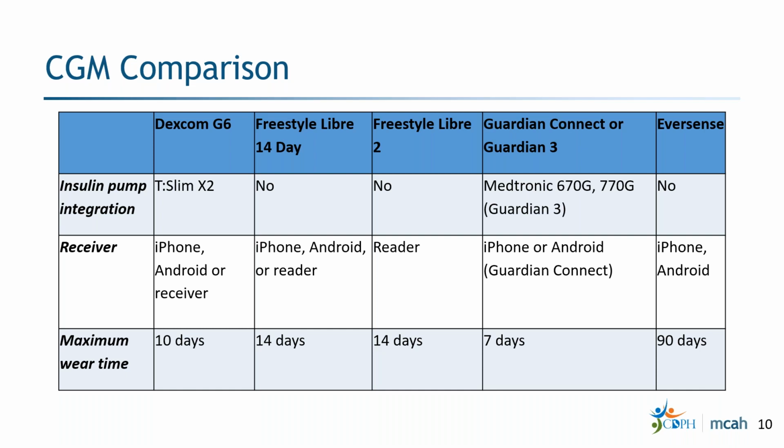The others at this time do not have the direct integration, although I do think it's important to note that both Libre 2 and Dexcom G6 have a classification called an iCGM, which means it is an integrated CGM. It means that the FDA has basically deemed that the accuracy is good enough that it can integrate with other devices like insulin pumps and connected pens.